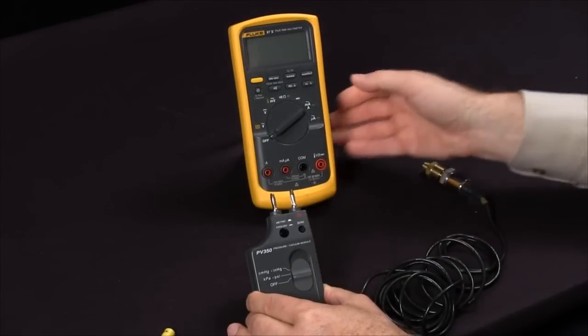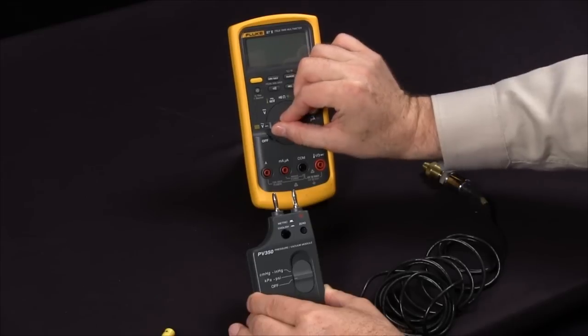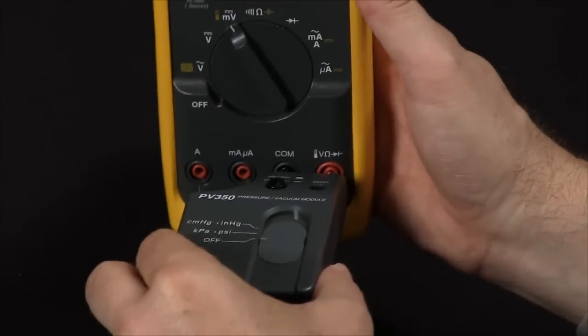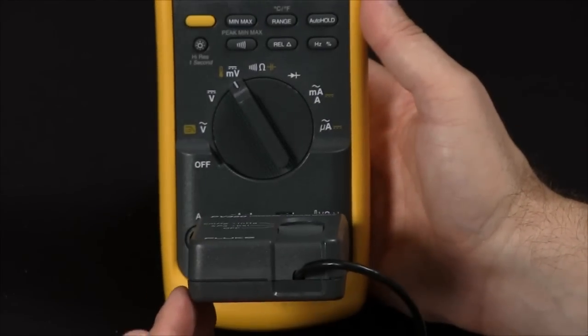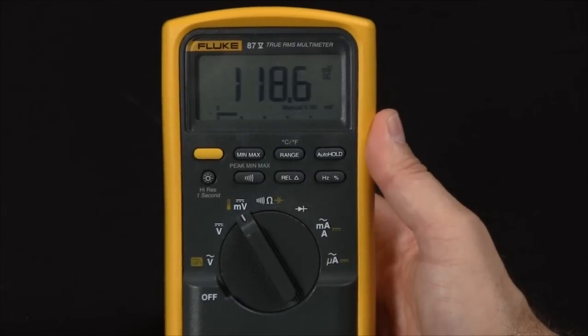We will turn this to off. Simply turn your industrial multimeter to a millivolt setting and insert the PV350 into your common and voltage jacks. You are expecting about 100 millivolt offset to indicate that the batteries are working within the module.